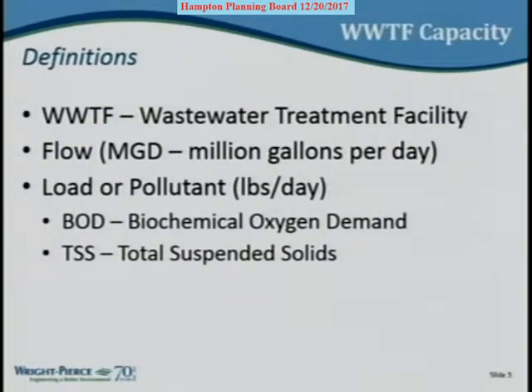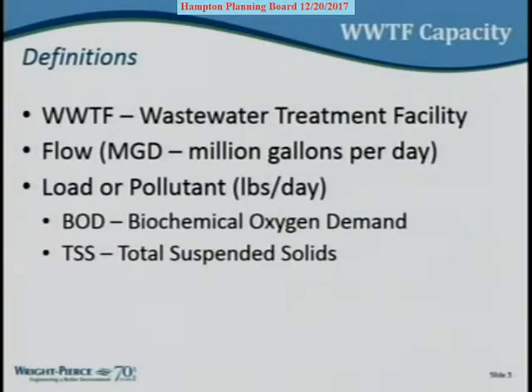Wastewater engineering is laden with acronyms, so here are the key ones. WWTF stands for wastewater treatment facility. Flow refers to the gallons of sewage coming to the plant, usually measured in millions of gallons per day or MGD. When we talk about load or pollutants, the two predominant measures are BOD - biochemical oxygen demand, what's dissolved or soluble in the sewage - and TSS, total suspended solids, which are suspended in the waste stream. We treat these different ways.